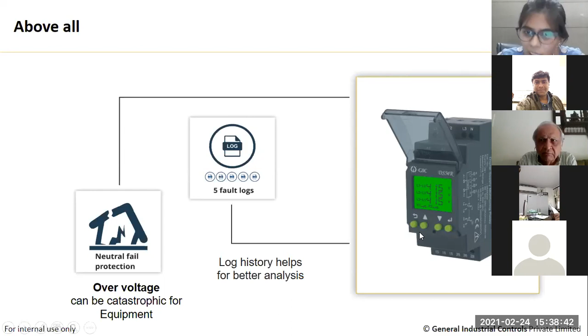Neutral fail protection is important because if there is any issue - suppose the neutral wire gets loosened or falls down, if there's something wrong with the neutral and the system doesn't trip, then anything can happen to the application, maybe because of increased voltage or current. So yes, it is important, and this is a feature in our device which we can enable or disable from the menu setting, using these keys, as per the user's requirement.